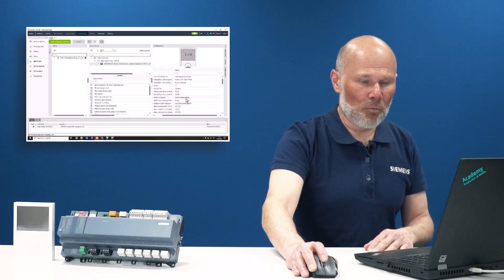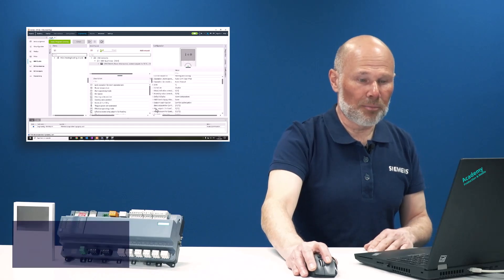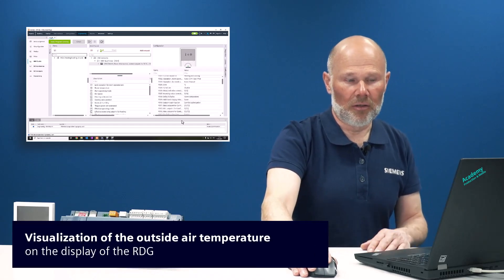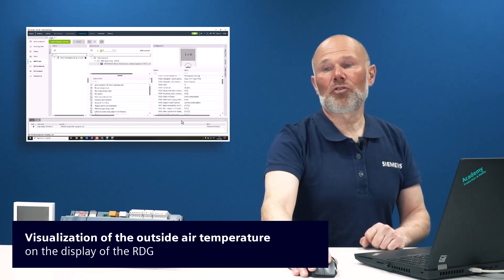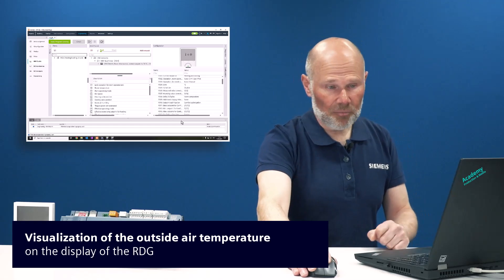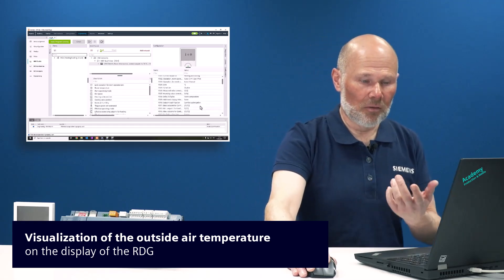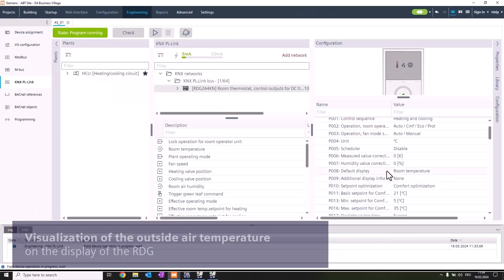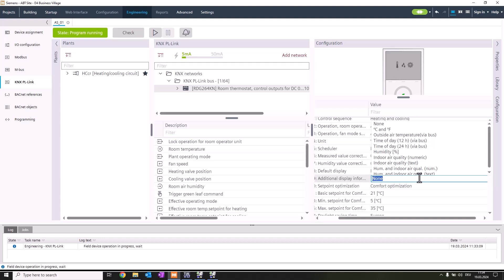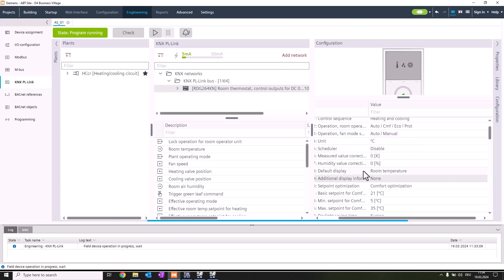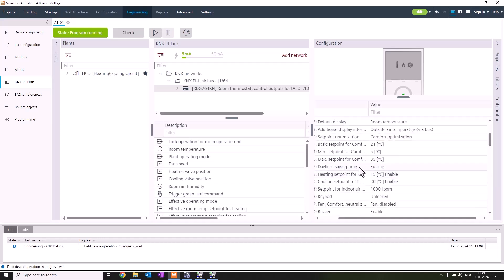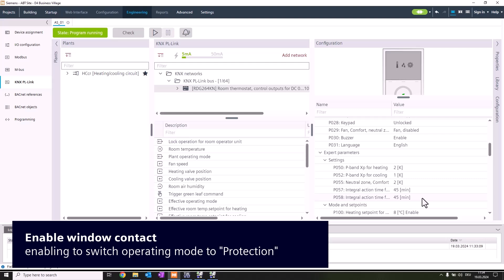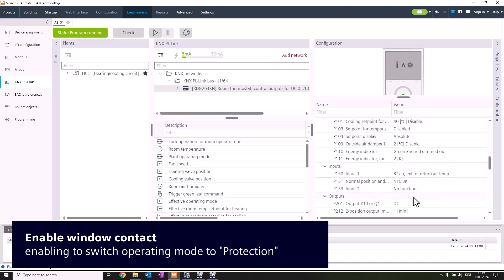Next we want to display on the RDG the outside temperature from the system, so we'll activate this parameter. In addition, we also want to use the window contact to make sure when the window is open we're switching from comfort to protection. This is input 2 we have to change.